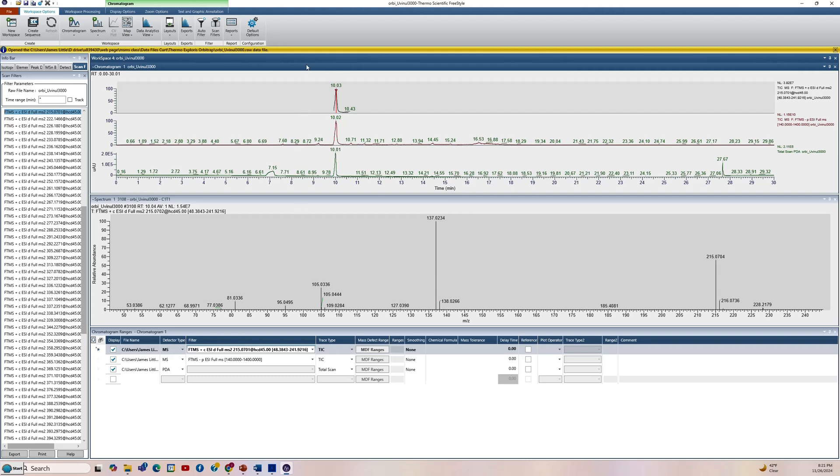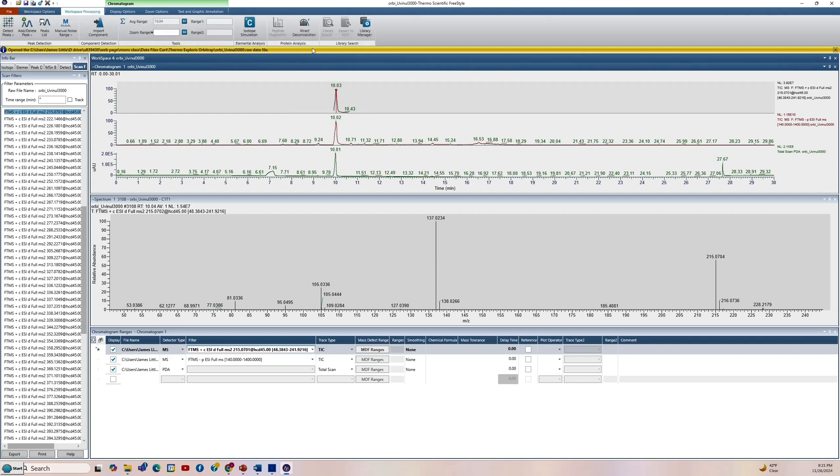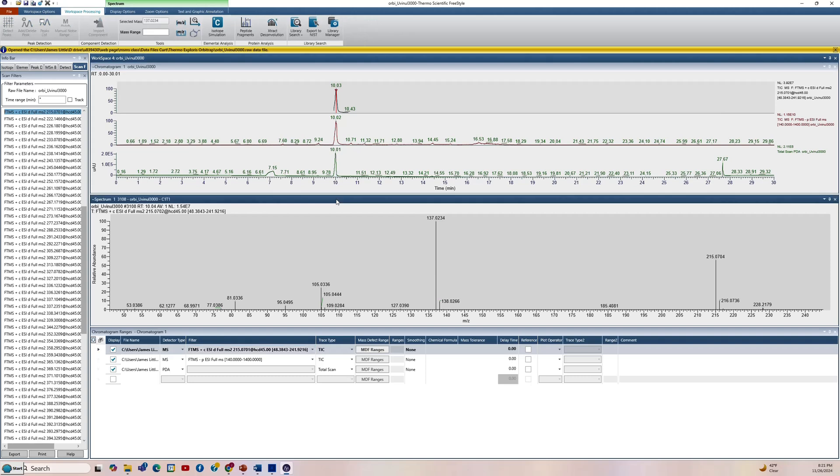If you had this selected at the top, say I've got the bar for the chromatogram selected, and you wanted to send it to the NIST search, you'd come up to the top and say workspace processing. And you'd see export export to NIST is grayed out. You cannot send it there. So you got to be sure the left click on the bar to get the MS-MS spectrum highlighted. And now you can export to NIST. If you did that, it would directly go to NIST and give you the results. I don't want to do that in this video because you have to look at another video to make sure that Freestyle is set up properly. And also the NIST search software is set up properly before you do the searches. So we'll stop at that point with regard to the NIST search.